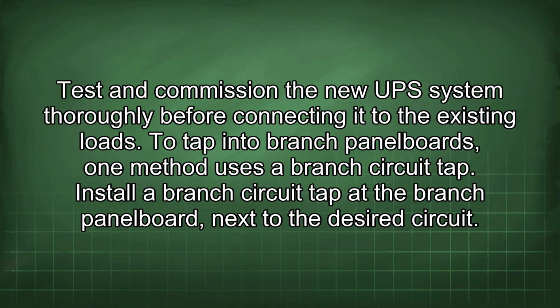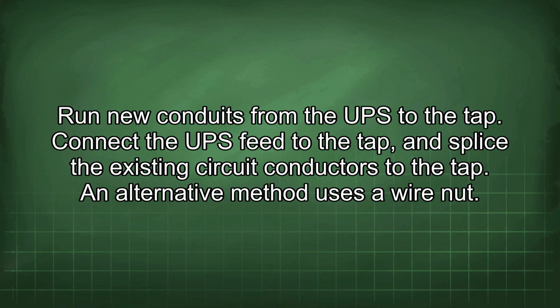To tap into branch panel boards, one method used is a branch circuit tap. Install a branch circuit tap at the branch panel board, next to the desired circuit. Run new conduits from the UPS to the tap. Connect the UPS feed to the tap and splice the existing circuit conductors to the tap.